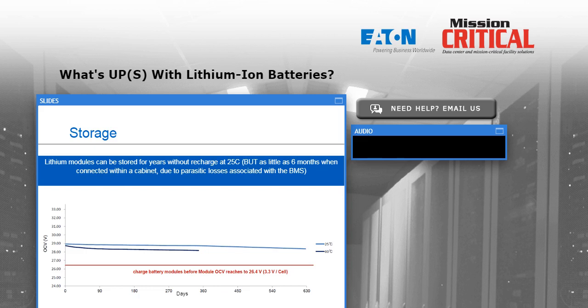Now, what about storage of batteries? It's always been an issue with traditional UPS batteries that if left in storage, especially in a warm environment, in as little as 6 months the batteries will self-discharge to the point where they're no longer useful or warrantable in a UPS application. So if my project was delayed and a battery sat in storage for 9 months, there was serious question as to whether it would be useful.